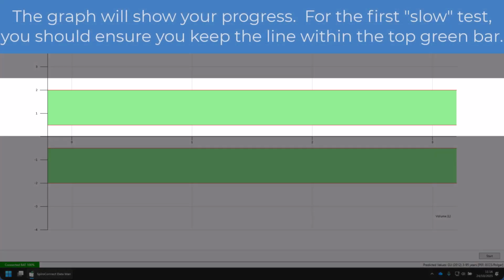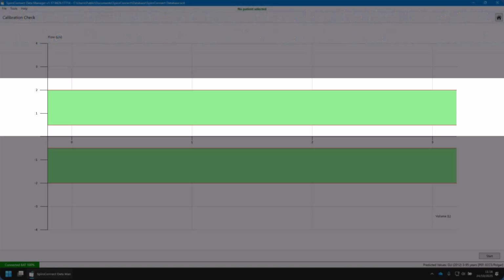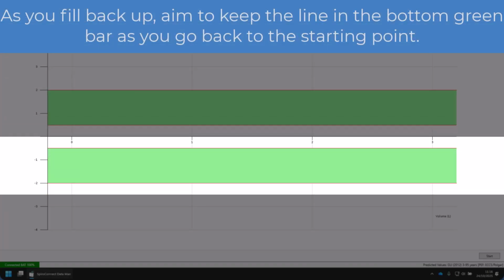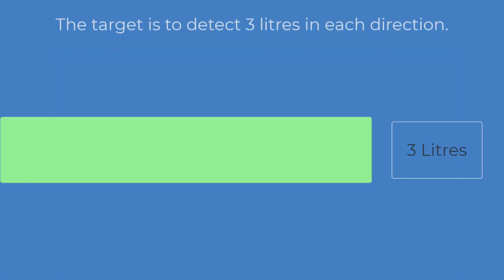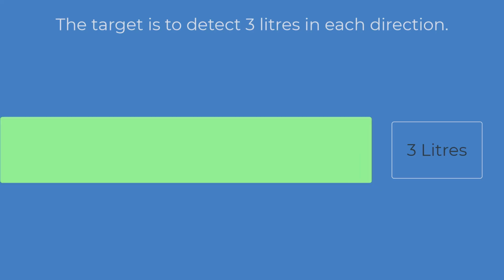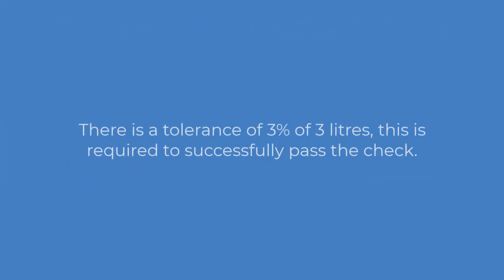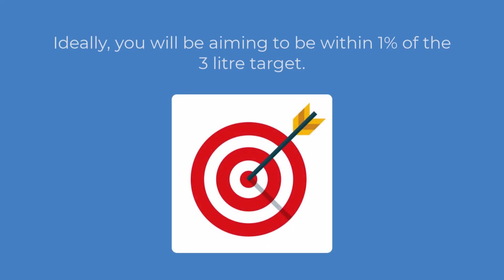For the first slow test, you should ensure you keep the line within the top green bar. As you fill back up, aim to keep the line in the bottom green bar as you go back to the starting point. The target is to detect 3 liters in each direction. There is a tolerance of 3% of 3 liters. This is required to successfully pass the check. Ideally, you will be aiming to be within 1% of the 3-liter target.